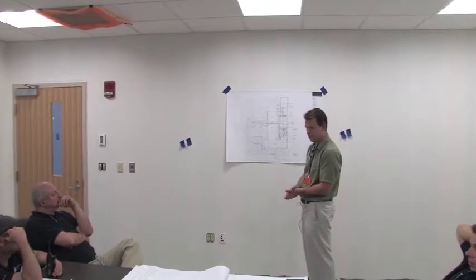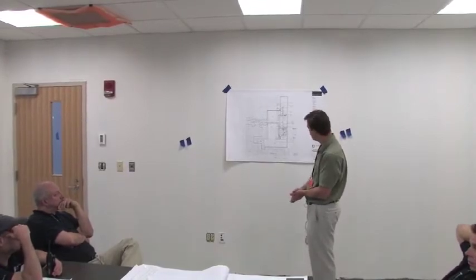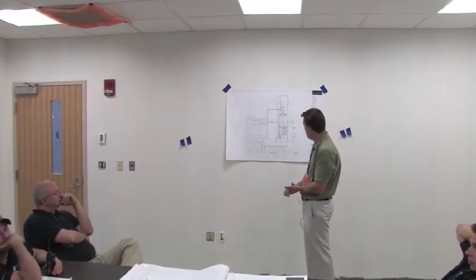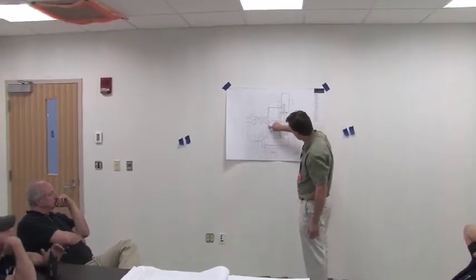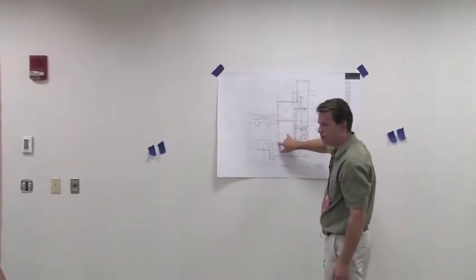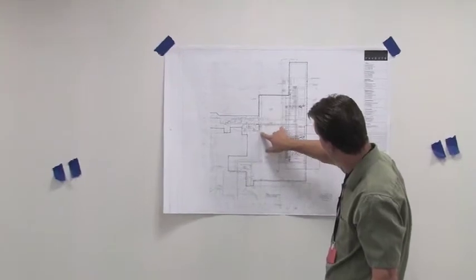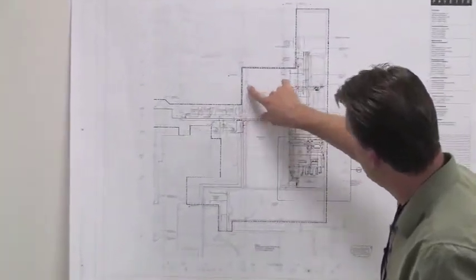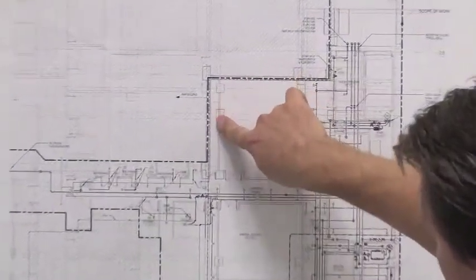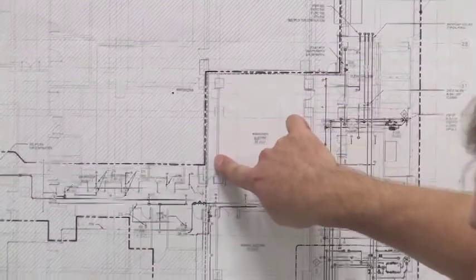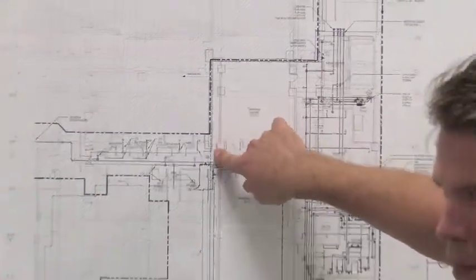Between the emergency electric room and the main building, there's a confined space, floor to ceiling, about 30 inches wide. Correct. That's the main electric room, that's sprinklered, but the one between the emergency electric and the main building, last time I checked, I wasn't here last week, there was no sprinkler system. Yeah, they finally sprinkled that. They did. Yeah. Their heads are in there now.